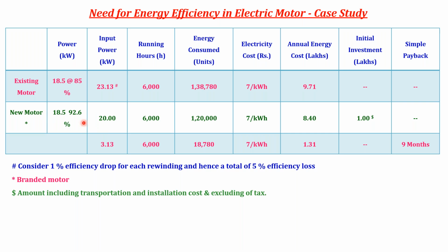Now the new motor is taking 20 kilowatt. The difference is going to be 3.13 kilowatt. The operating hours are going to be 6,000 hours, and the energy consumed is going to be 18,780. If the rate is 7 rupees per kilowatt hour, then the energy loss is going to be 1.3. The same branded motor or even a higher branded motor, including the transportation cost, is going to be almost 1 lakh rupees, maybe around 1 to 1.5 lakhs.